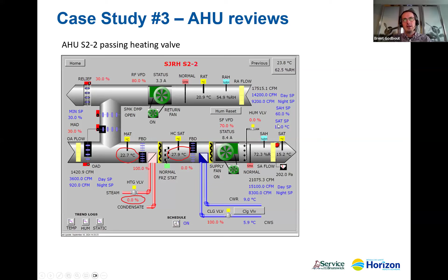Graphically, this is some of the benefits of these tools. This just shows our temperature indicator before the heating coil valve, and the top line is after the heating coil valve, and it's showing that 6 degrees temperature increase. Started way back on September 11th. And then it went for quite some time until the 19th when I found it. And again, it's just those competing priorities. The facilities folks have so much going on that they can't always be on top of these things, and it may have got bumped down to a lower priority, so to speak.